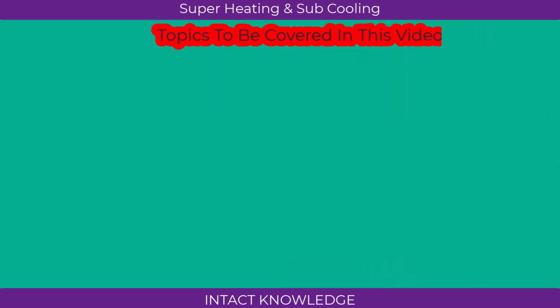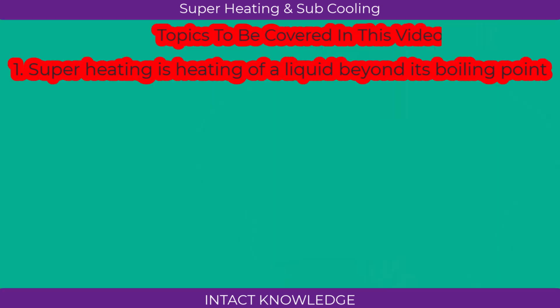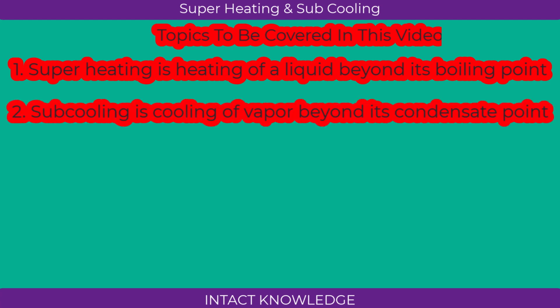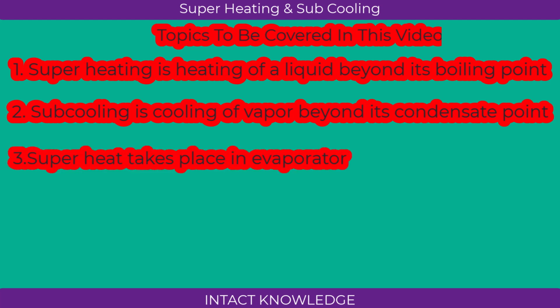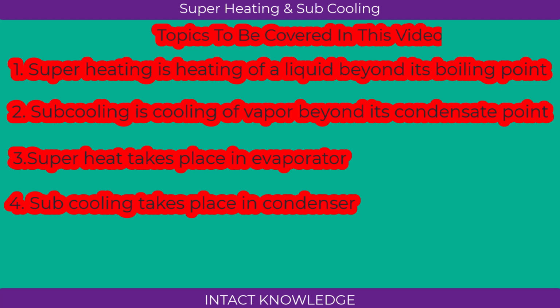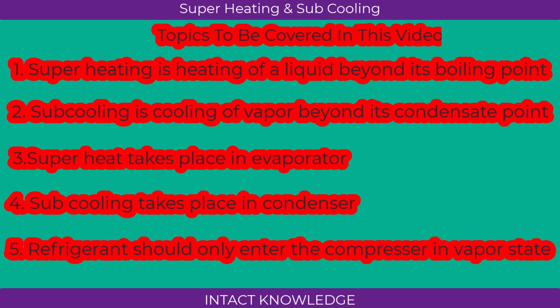Important points that can be covered in this topic are: superheat is the heating of a liquid beyond its boiling point. Subcooling is the cooling of vapor beyond its condensate point. Superheat takes place in the evaporator. Subcooling takes place in the condenser. Refrigerant should only go in vapor state while going inside the compressor, because only vapor can be compressed. Liquid cannot be compressed. This is the explanation of superheat and subcooling.